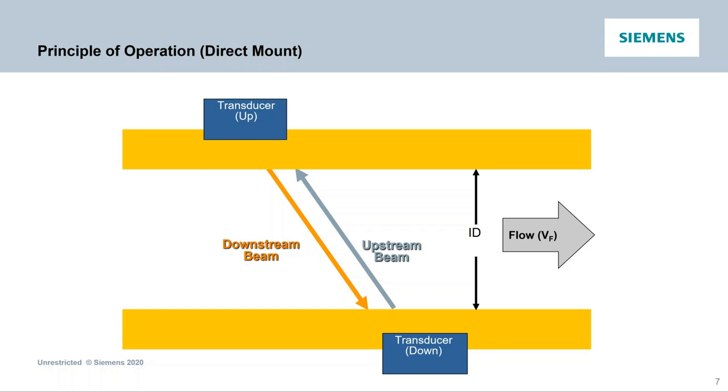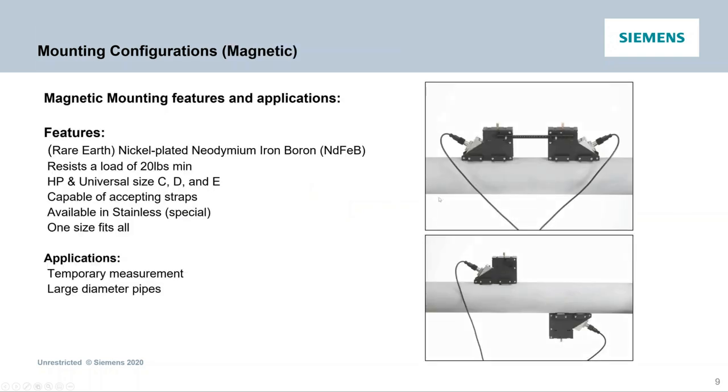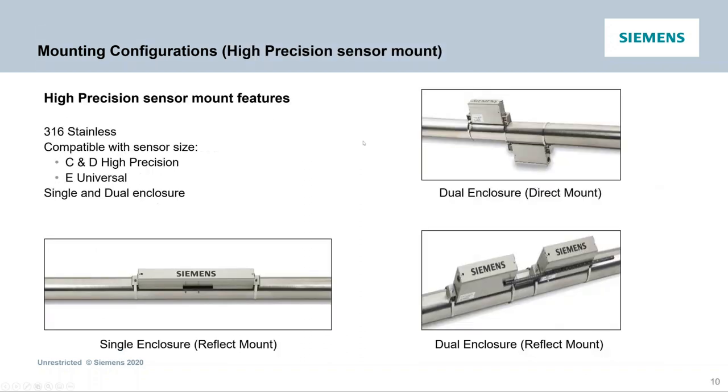Going over some of the mounting configurations: in the field, you have mounting frames with stainless steel straps, all IP-rated. You've got ladder chain mounting straps for quick temporary measurements — if you want to go out and do a check measurement or get some readings on a line. There are also magnetic mounting frames that are adjustable and work with various size transducers in your kit — good for large diameter pipes, so you don't have to put a strap or ladder chain around the pipe. And then for robust, harsh environments, there are High Precision sensor mounts in stainless steel.